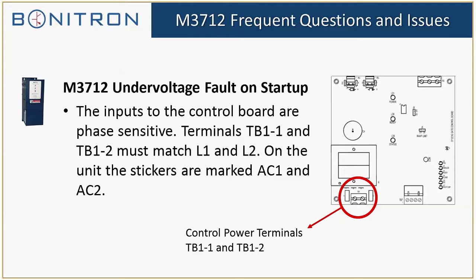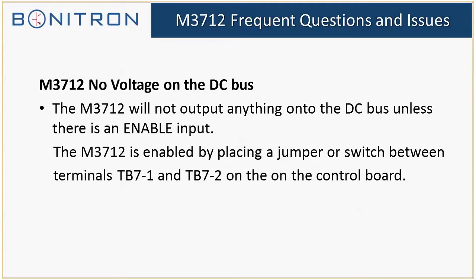The only issue is that the control board needs to be in phase with L1 and L2. If it isn't, you will get an undervoltage fault right when you power on, if the terminals that are marked AC1 and AC2 are flipped and out of phase with L1 and L2. The other issue I have with the M3712 single phase power supply is that they'll start it up, they'll have the phases correct, but they won't see any voltage on the DC bus. That's basically because the M3712 does require an external enable.